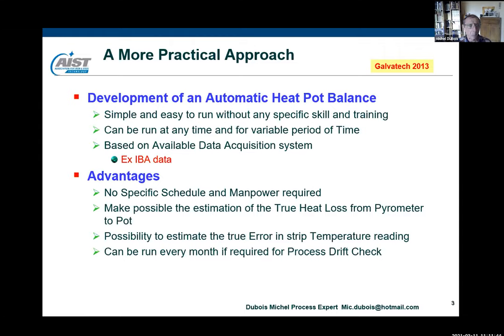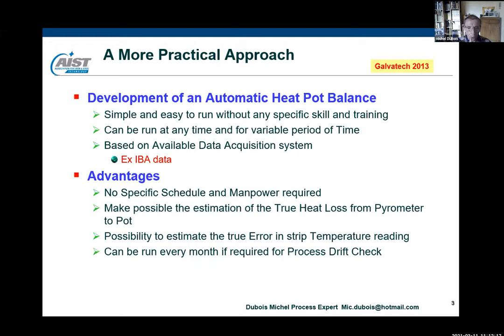The advantage of this approach is no specific schedule or manpower required — you take the classical data available. It makes possible the estimation of the true heat loss from the pyrometer to the pot, which is very important because you have two unknowns in the system: the heat loss and the offset of the pyrometer. It can be run every month if required. I recommend doing this once a month to check process drift, because when the process drifts smoothly, you never see the difference. In galvanizing, once a big crisis of defects appears, you cannot compare to what it was one year before.